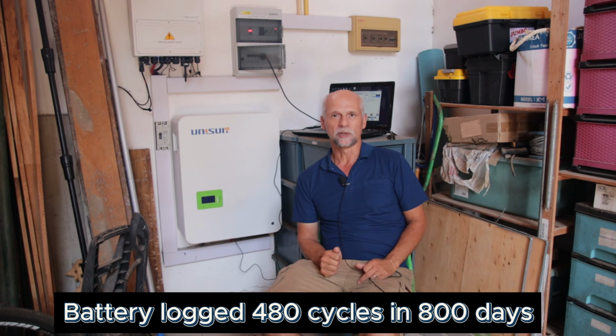This system was mainly responsible for providing backup power for our water system, and there's also one guest bungalow connected. I've set a reserve of 30% on this system, so the depth of discharge in the worst case was always just 70%. Because this battery would usually just deal with the water system, it would only discharge by 2 kilowatt hours a day on any given day. And if the bungalow is occupied, which happens maybe half of the year, then it would go down to 30%.